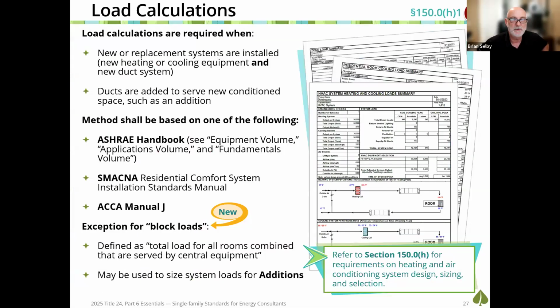All right, moving on to some other mandatory requirements. Load calculations. Load calculations have always been a mandatory requirement. We have to determine the heating load based off of the geographic area the project is located in. We're talking about heating loads during the winter months, cooling loads during the summer months. These must follow one of three methodologies: the ASHRAE Handbook Fundamentals, SMACNA, or ACCA Manual J. The code does have a new requirement for additions, saying that rather than doing a room by room load calculation, if you're doing an addition, you can assume a block load, meaning you can take the entire zone of the addition and the existing building to determine the heating and cooling loads. Whereas for new construction, the code implies that a room by room load calculation be done.